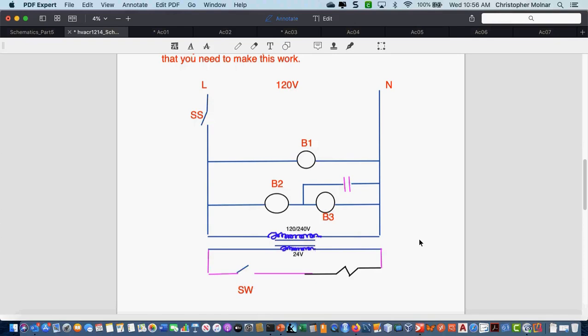Labeling. Labeling, right? Because if I had more than one relay in here, I'd never know what relay coil controls what relay contact. So I got to be very careful. Everything needs to be labeled. It's really important as the schematics get more and more complex. So we know that this relay coil controls this set of contacts. Does anybody have any questions on this diagram, including the bypass? Any questions on the sequence of operation?